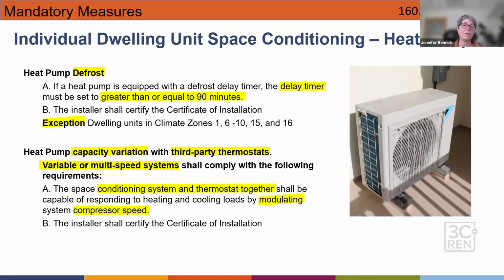And for the heat pumps that have third-party thermostats, we're finding that there's this capacity variation. So they call it heat pump capacity variation with third-party thermostats. Basically, what they're saying is your conditioning system and the thermostat together shall be capable of responding to the heating and cooling loads by modulating the system compressor speed. So again, this is a mandatory requirement. Your mechanical engineer who's specifying this equipment should really be considering what's going on with the thermostat that is being chosen to go with this equipment so it meets this new requirement.